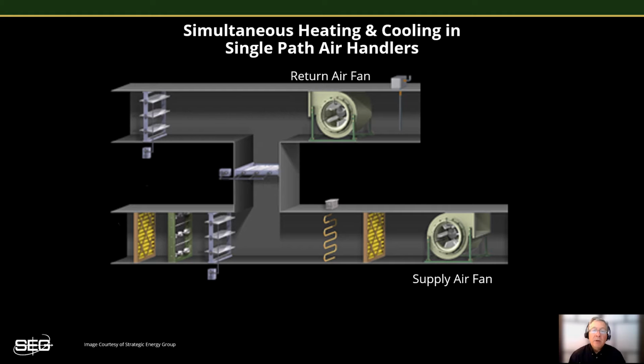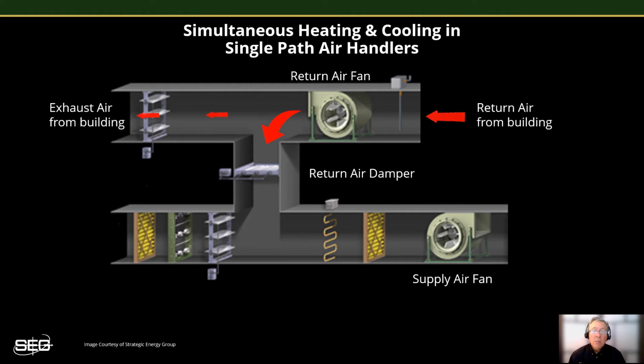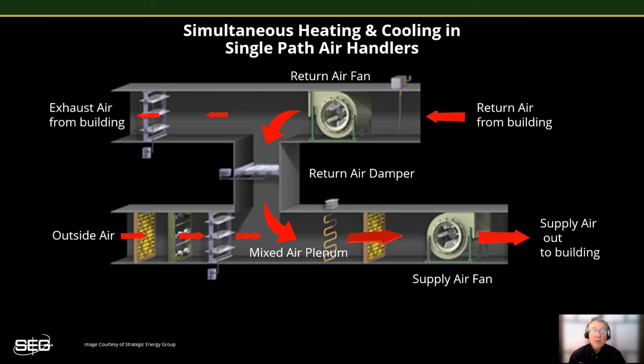Here we have a graphic depicting a typical single-path air handler. The return fan draws air back from the building to be conditioned, in other words, reheated or cooled as needed. And in this case, most of the returning air is drawn through the return air damper, while a small portion is being exhausted. The return air then gets mixed with fresh air being drawn in from outside in what's called the mixed air plenum. It then passes through a bank of filters and then across the heating and cooling coils to get pressurized as it passes through the fan, leaving the air handler as conditioned supply air, and is then distributed out to the various zones that it serves.